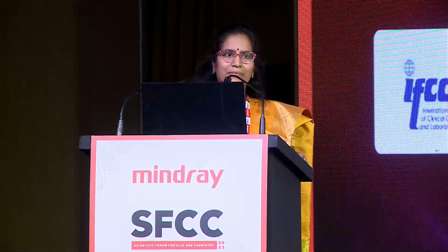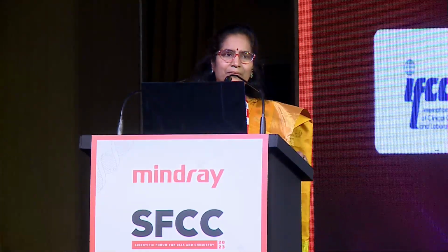So we have done between two different manufacturers. I would not like to take names at this platform, but the variation in TSH was more than 30%. And when I looked at international literature, there is a difference as high as 50 to 70% amongst different analyzers, and there is something known as harmonization of TSH that is being tried but not yet fully successful. So what I would recommend is that if in your laboratory you are using more than one analyzer, then you must establish a Deming regression curve and a correlation factor amongst those analyzers, and at least apply those factors in one of the two machines.